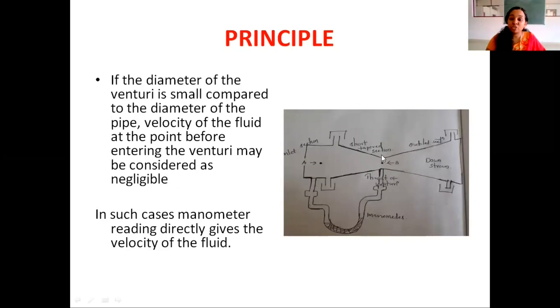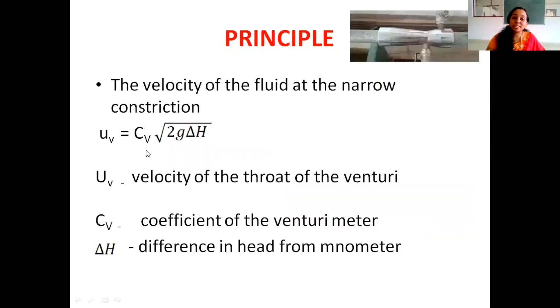If the diameter of the Venturi is small compared to the diameter of the pipeline, then the velocity of the fluid at the point before it enters the Venturi may be considered negligible. In such cases, the manometer reading will directly give the velocity of the fluid passing through the Venturi. By using the formula uv = cv × √(2g·Δh), we can determine this velocity. Here, uv represents the velocity at the throat of the Venturi, cv represents the coefficient of the Venturi meter, and Δh is the difference in pressure head from the manometer.